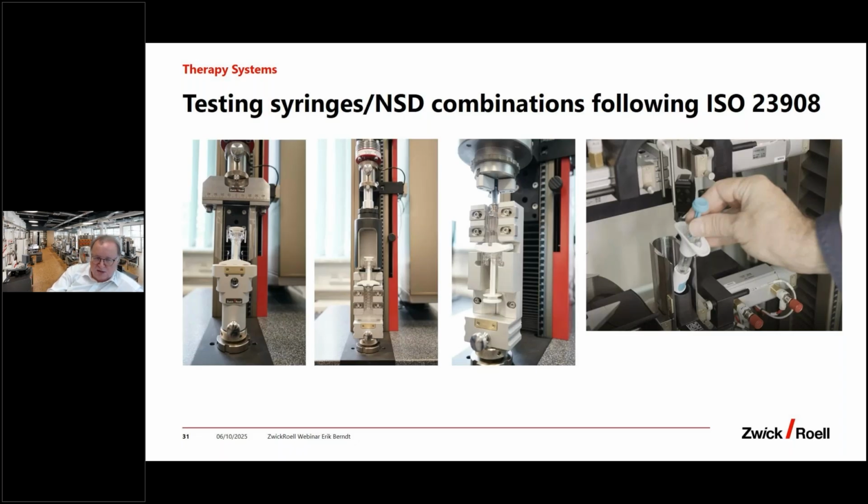This is this metal ball test inside. There are different references inside here. We're also doing an amendment in the ISO, but at the end we are offering the different tools also to measure this hidden needle in the needle safety device, the pre-filled syringe with needle safety device, or an autoinjector after the needle shield is blocked.